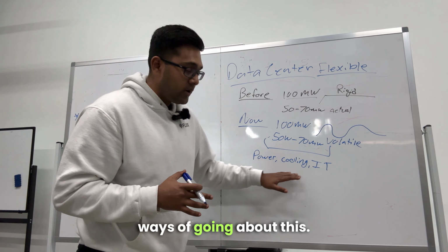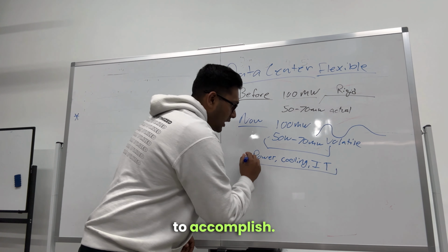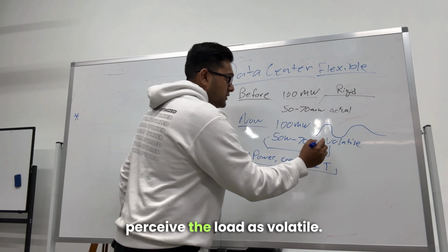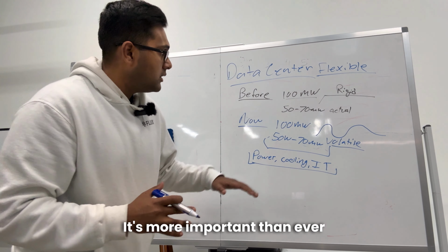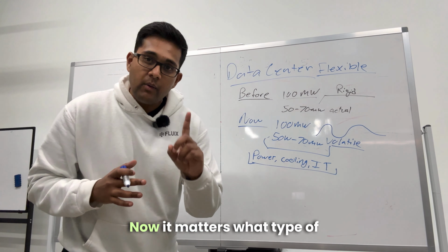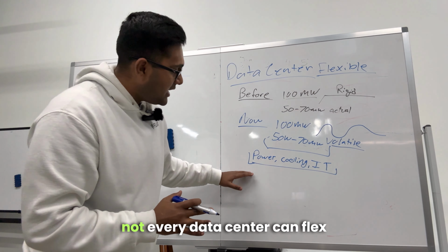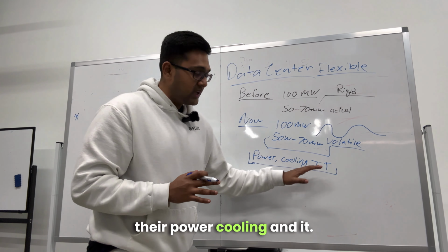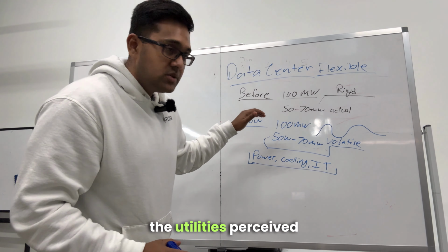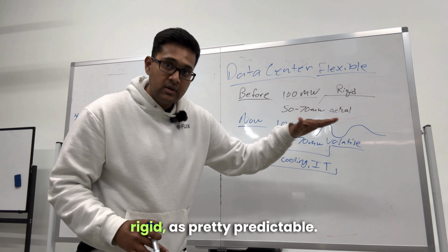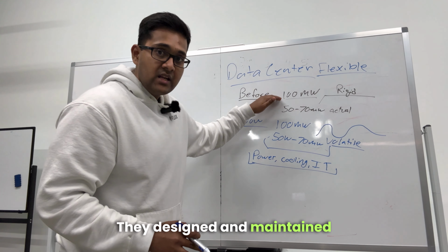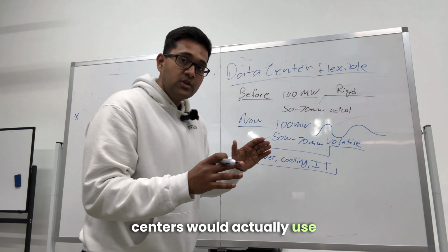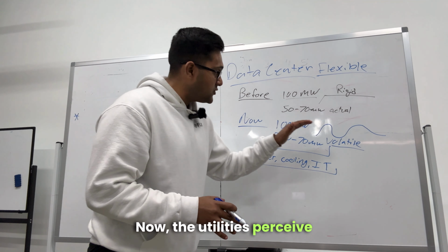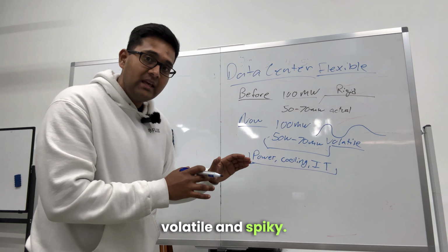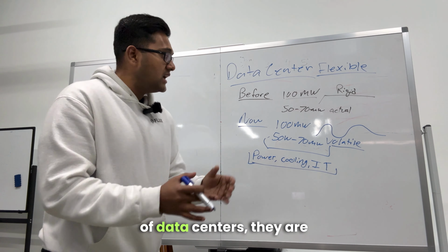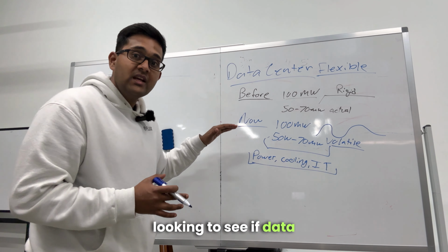There are many different ways of going about this, and it's quite complex to accomplish. Because utilities now perceive the load as volatile, it's more important than ever that data centers can become slightly flexible. It matters what type of data center you have, because not every data center can flex their power, cooling, and IT. So to summarize: before, utilities perceived data center load as rigid and predictable, designing and maintaining power for the peaks even though data centers used less. Now utilities perceive data centers as extremely volatile and spiky, and due to congestion and the rapid rise of data centers, they're looking to see if data centers can be flexible.